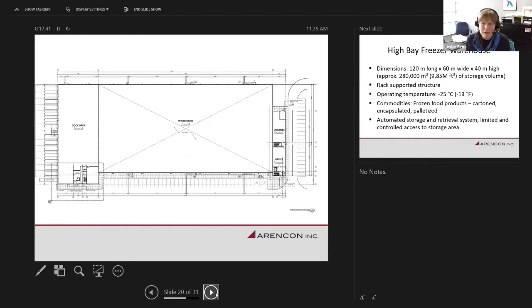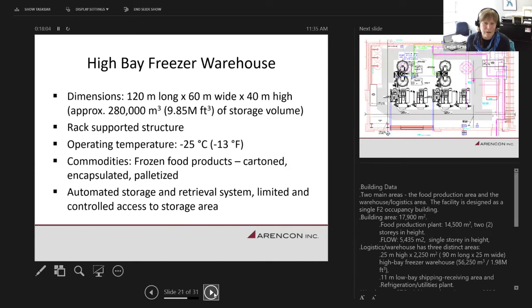I may have some slides out of order. So, a typical arrangement of a high bay freezer warehouse: you have a large warehouse. In the central area, you'll have a dock area for the automated retrieval system to load and unload and to transfer to trucks. You'll have a utility space. This is the one we're looking at in Oakville. It's going to be 120 by 60, long by wide, but 40 meters high. So we're up into the 10 million cubic feet of storage by the time you put all these dimensions together. It will be a rack supported structure, minus 25.